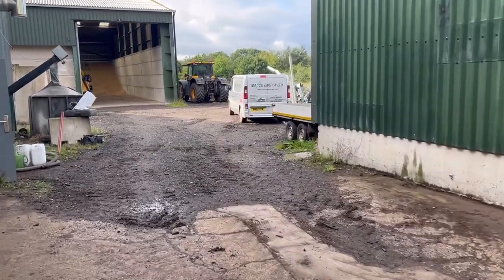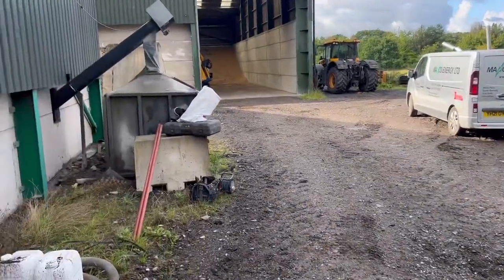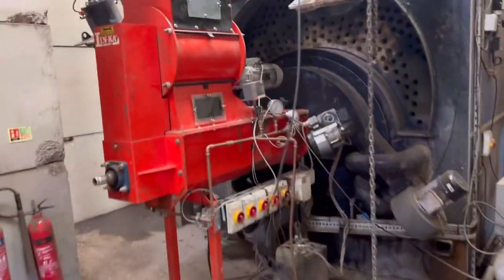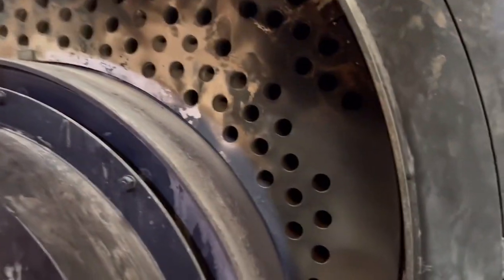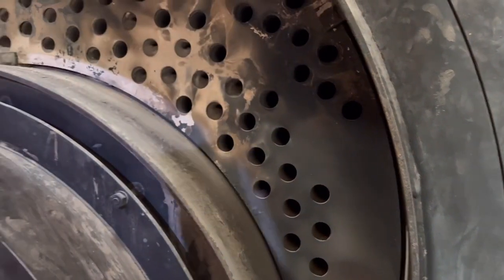Noticed a slight leak on the boiler yesterday while we're fixing the ash auger. So Chris is here now, going to do a bit of TLC on it. Got it opened up now, going to clean the tubes out. That's where the hot air goes through, and all around it is water.